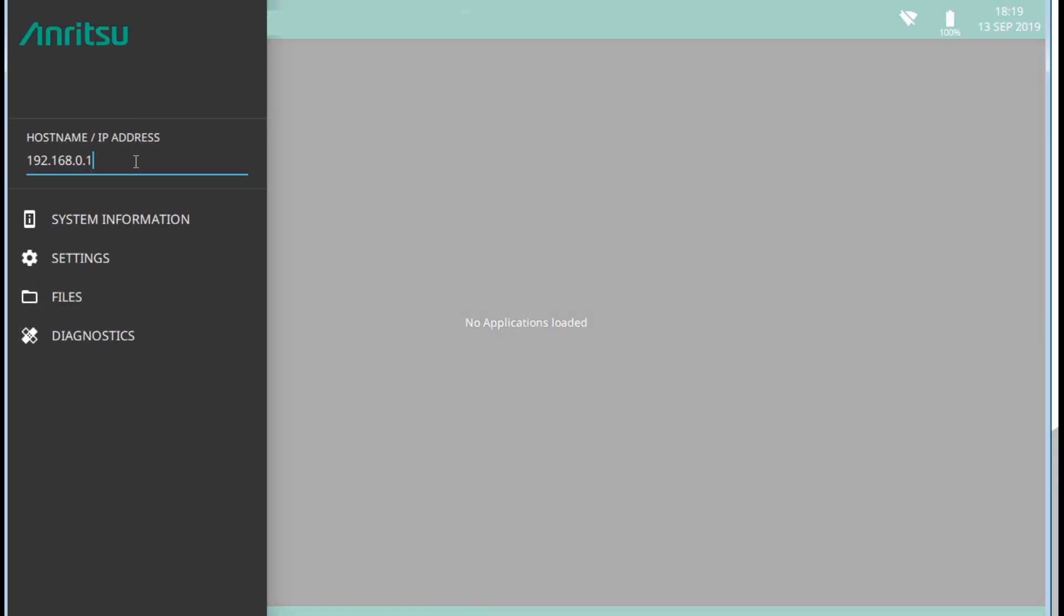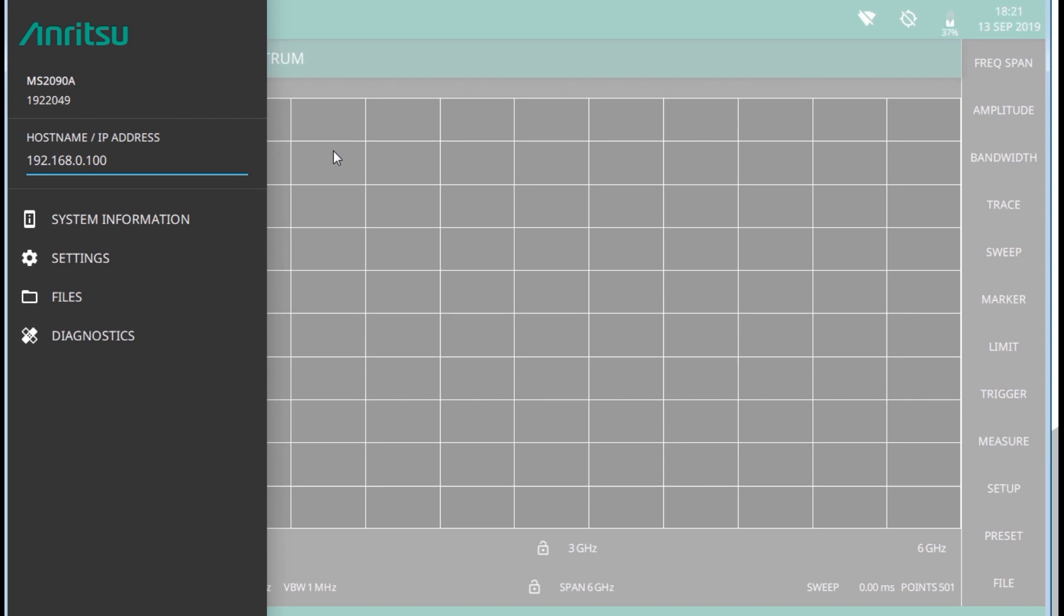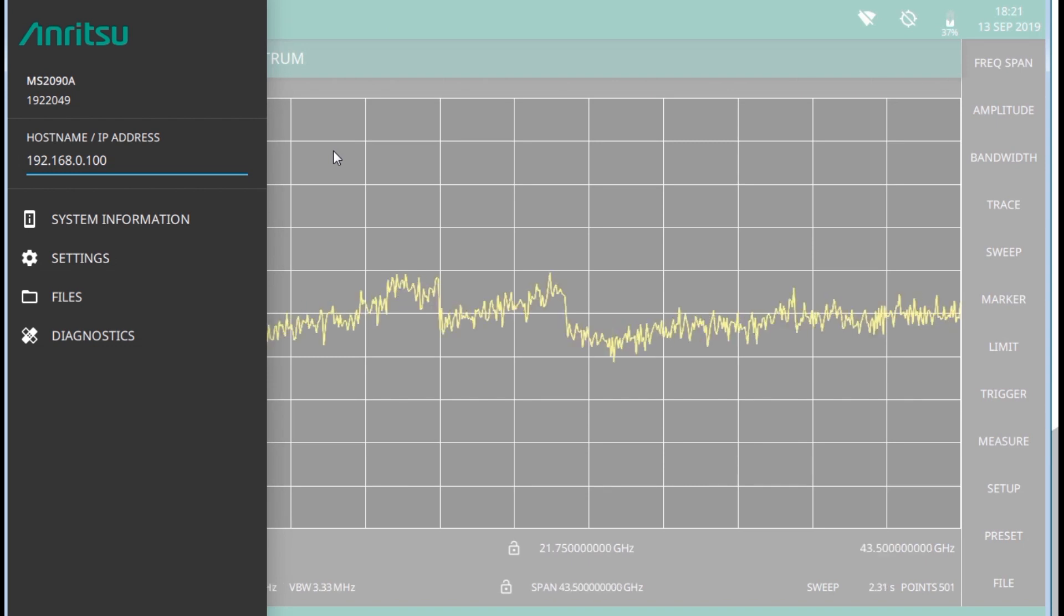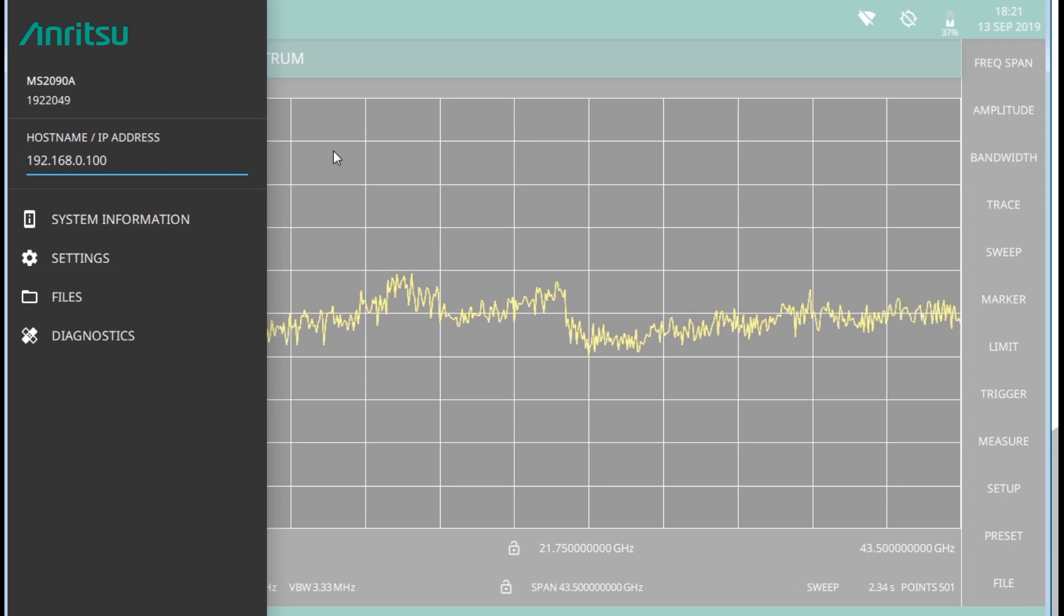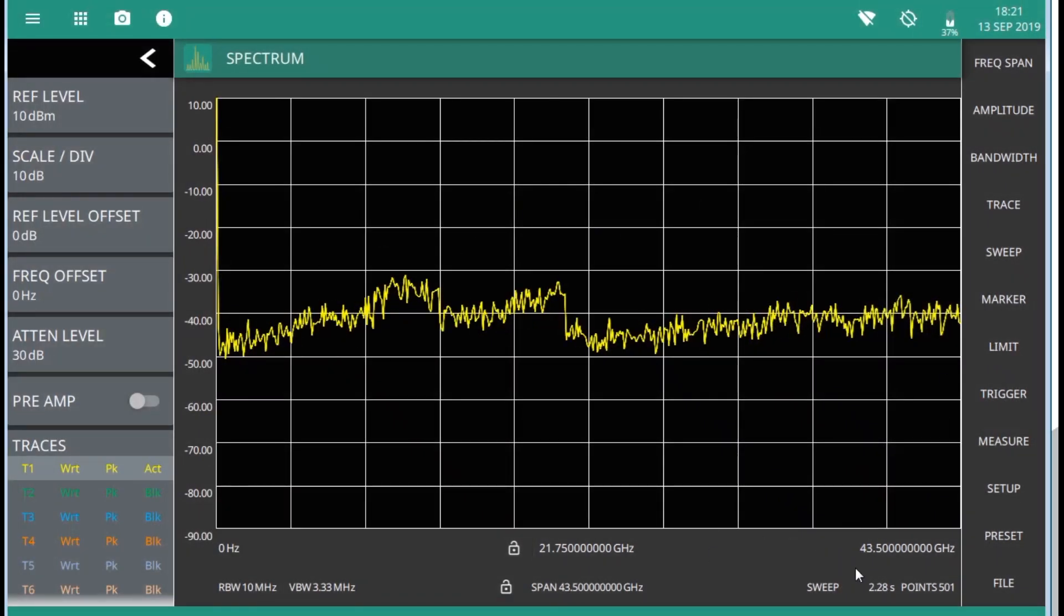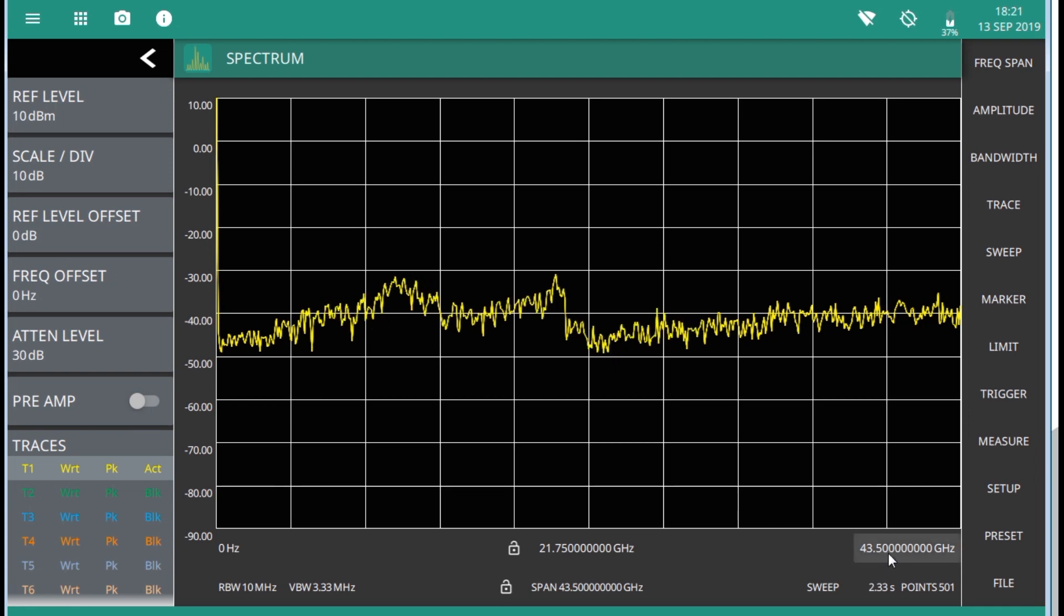And now, going into the demo session. The MS-2090A FieldMaster Pro software controls all instrument functions. The software runs locally on the instrument and primary operation is through the touchscreen display. For this demo, I'll be using remote control software. I've already launched the MS-2090A software from a shortcut on my desktop. You can find the MS-2090A software on our website at anritsu.com. I'm going to type in the IP address of the MS-2090A sitting right on my desk, which is manually configured under the Ethernet settings of the instrument. And now we have a spectrum trace sweeping at 43.5 GHz.